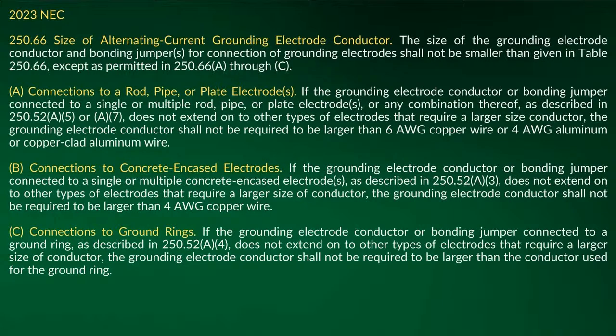Okay. Well, yeah. And that's why I wrote in my myth the sole connection, because you are permitted to share electrodes. Sure you are. Like if you have a certain size, then you're permitted to share building steel and ground rod. Your building steel is going to be way larger than whatever your ground rod is going to be. It depends on how it's set up, if it's looped or not. And most of the time what they do, they come up, hit a terminal bar, and everything comes up whatever size it is. And then from there, whatever the largest is goes to the panel board or service equipment.